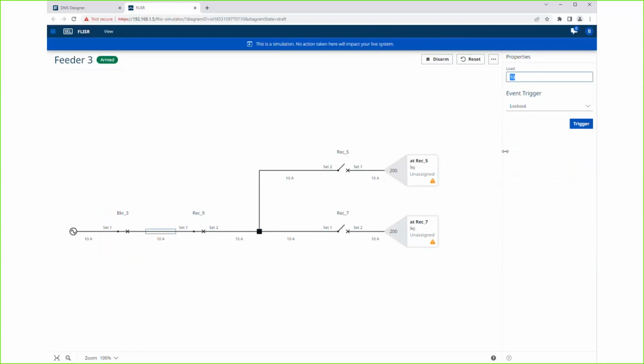So if I click on this line segment between breaker 3 and recloser 9, I can apply a fault that results in a lockout. And you can see that breaker 3 locks out all by itself. That's the simulator simulating what the real world would do. FLISR is reacting to it. It doesn't know that this isn't real. It's sending controls that would go out over DNP if we were not in a simulated environment.